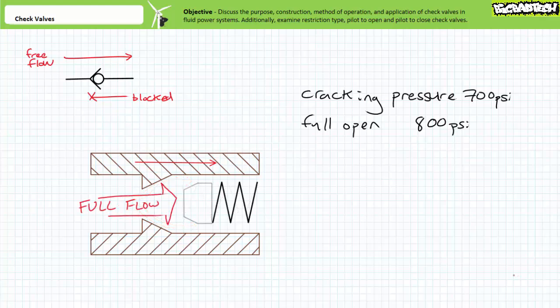Finally, when pressure hits 800 psi, the check valve fully opens and diverts all flow to tank. The system is therefore limited to a maximum pressure of 800 psi. While effective, this primitive means of pressure relief isn't exactly the most elegant of methods, principally because of the large differential between cracking and full open pressure inherent to the direct acting nature of this primitive pressure relief valve.